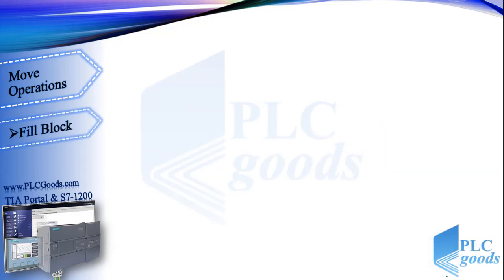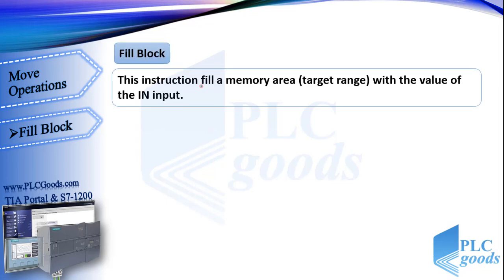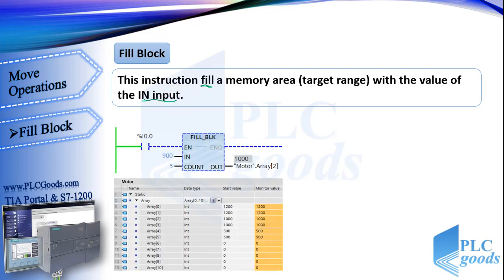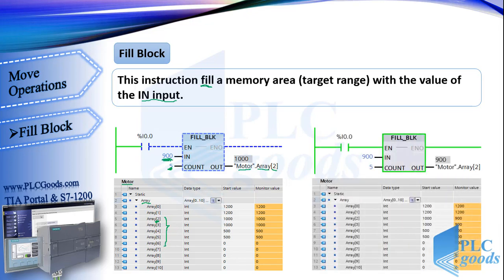The next instruction is similar to move block. It fills a memory area with the value of the IN input. As you see, its output refers to the motor data block and array with number 2, and its count value is 5. So if I activate this contact, the fill instruction writes number 900 on all 5 selected addresses.